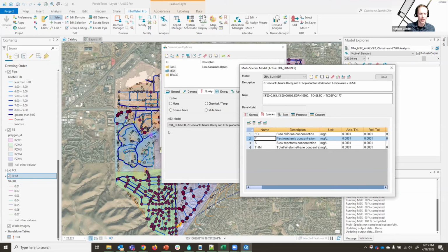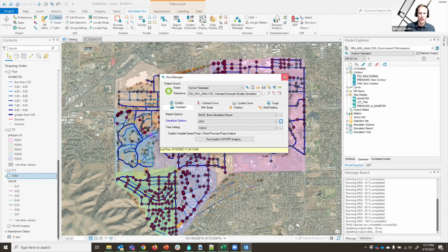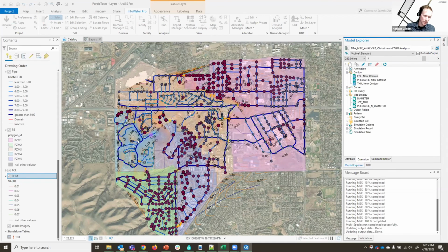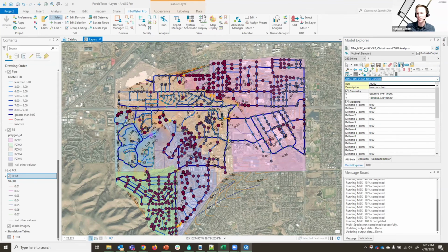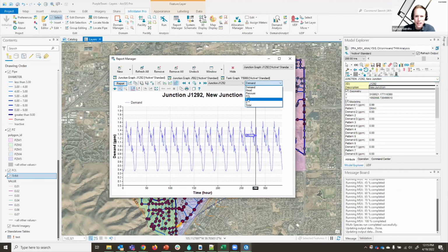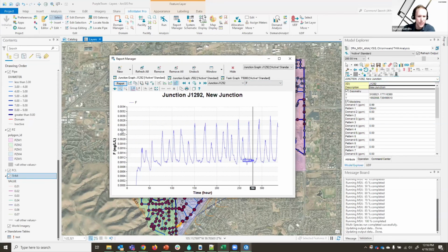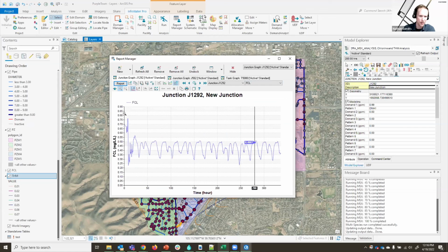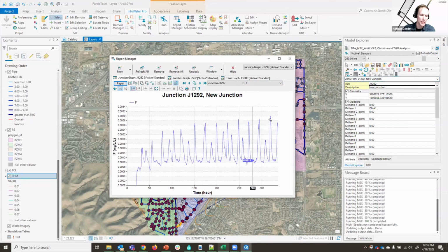In general, I didn't pick the right nodes to show it, but we'll see that the F that comes out of the treatment plant decays really quickly, and it brings down the chlorine. And usually it doesn't make it too far out. If I grab one of these nodes farther from the treatment plant, let's just take a look at the F out here. So it's 0.0024. Maybe it's still out here because the chlorine itself has decayed. Oh, no, it's not too low. It's kind of flatlining. But yeah, so the F usually decays. It creates that initial slope. That's how you use it.